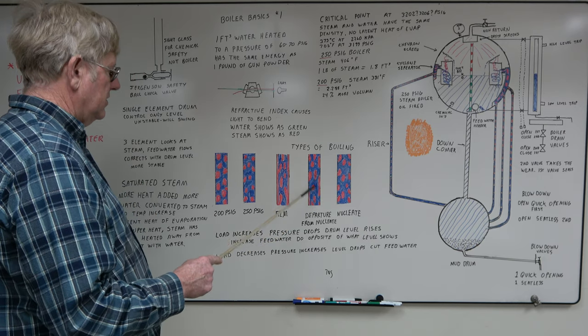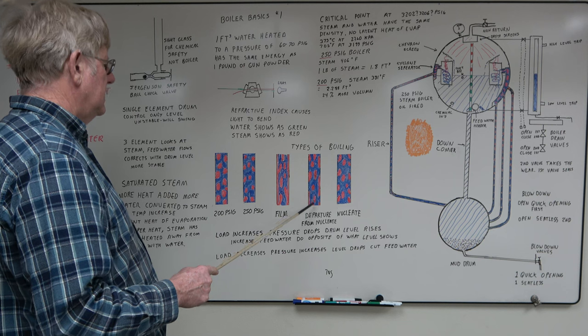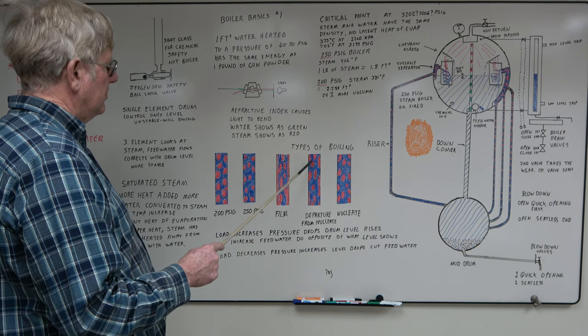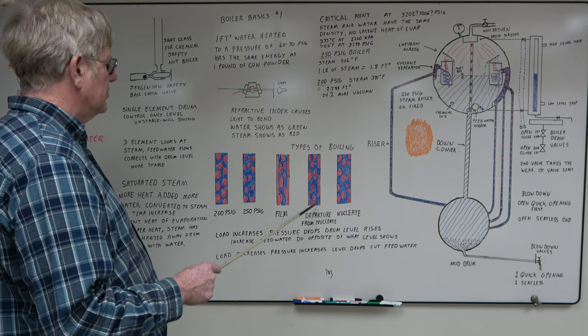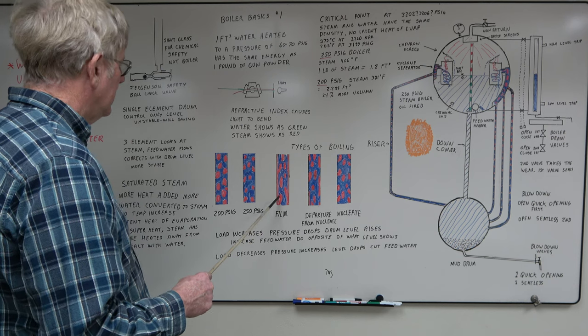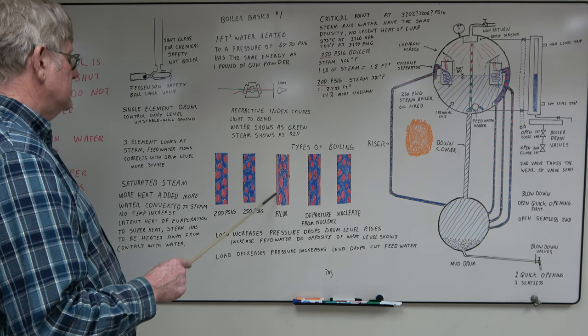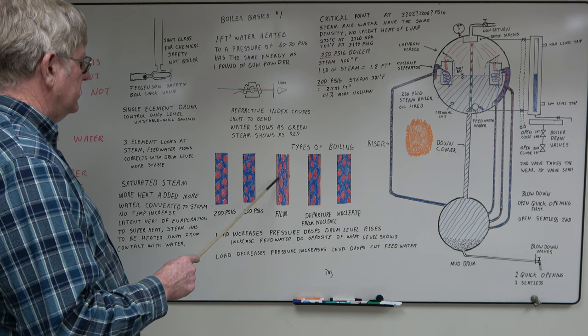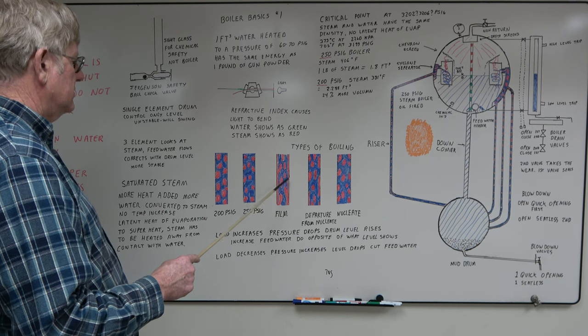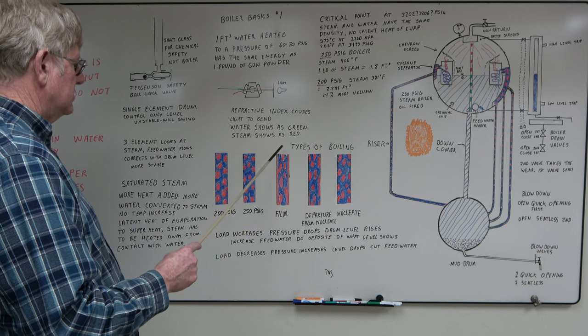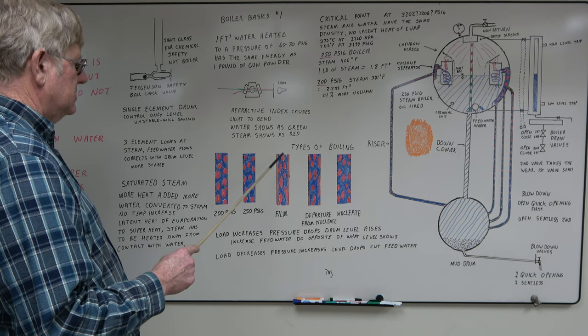Departure from nucleate boiling, starting to get sheets, larger voids. That's from over firing the boiler. You're starting to lose some tube cooling. Then you have film boiling. That's getting sheets of steam forming on the tubes. You're losing a lot of cooling as this is kind of insulation here. High heat loads. Somehow you've lost flow in the tubes or firing is too hard.